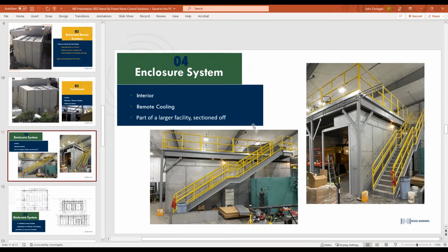It was a remote radiator setup, which is important in this case because the radiator and the large volume of air that had to go through there to service the cooling from the radiator fan and radiator are outside. So they really just have 2 big engines running that need nominal cooling through that room, and the liquid cooling is coming from outside. So here's an example of an enclosure that's really just an enclosure with a few special attributes.